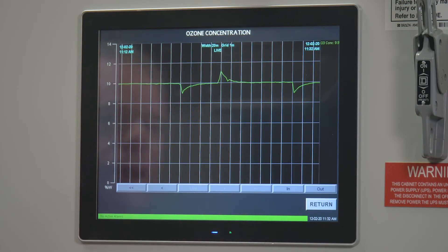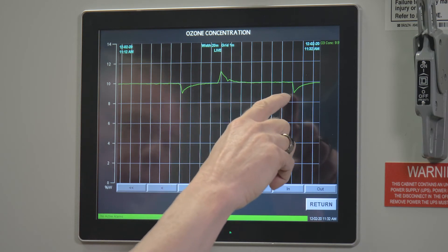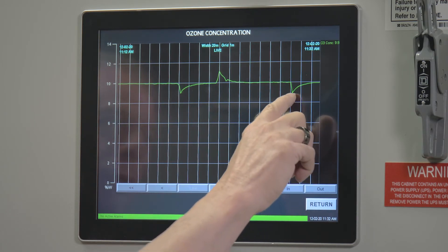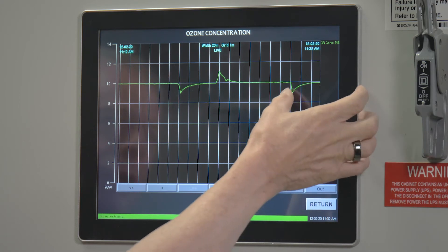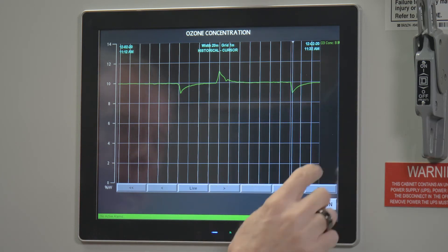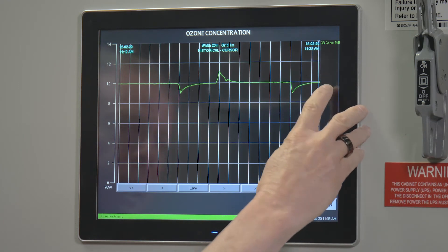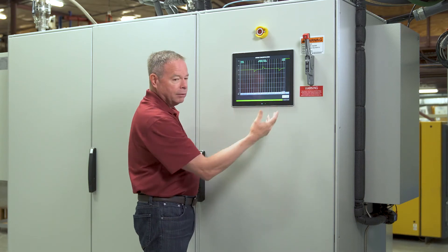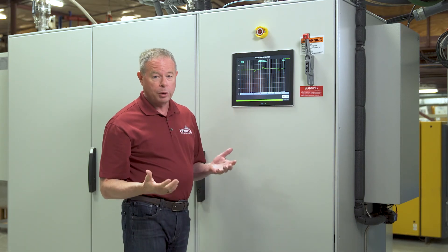Let's take a look at the graphs — we go to percent concentration. You can see where we were running right along at 10% concentration, then we lost the quad. Look at that beautiful exponential response back to 10%. The failure occurred right at 11:30 AM, and we're right back up to 10% right now at 11:32 AM — a two minute recovery period. Pretty impressive.